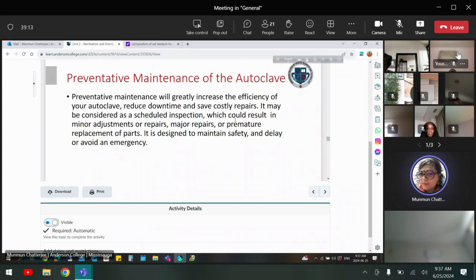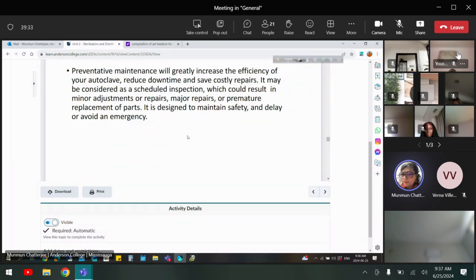Preventive maintenance will greatly increase the efficiency of your autoclave, reduce downtime, and save costly repairs. It may be considered as a scheduled inspection, which could result in minor adjustments or repairs, major repairs, or premature replacement of parts. It is designed to maintain safety and delay or avert emergencies. So daily maintenance is important for all the equipment, not only for the autoclave. And if there is any problem, immediately report it so that it does not get further damaged.